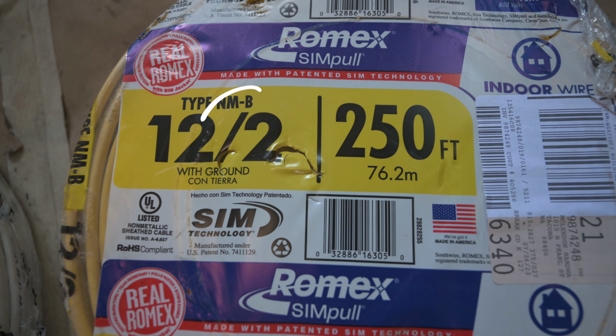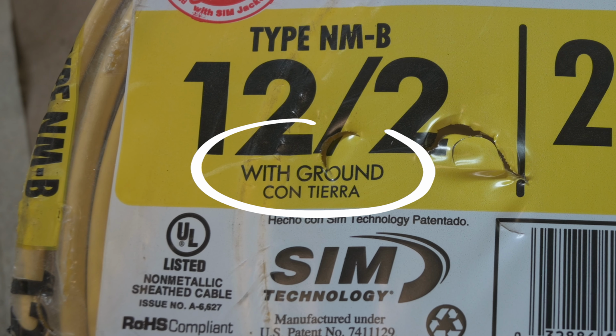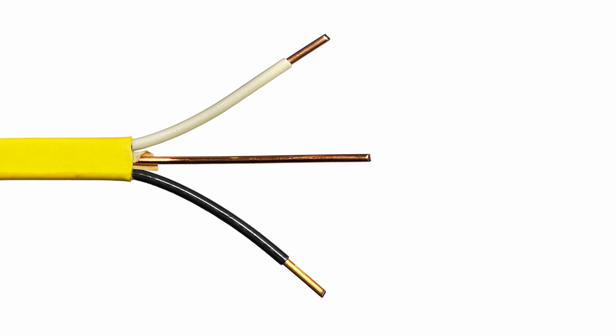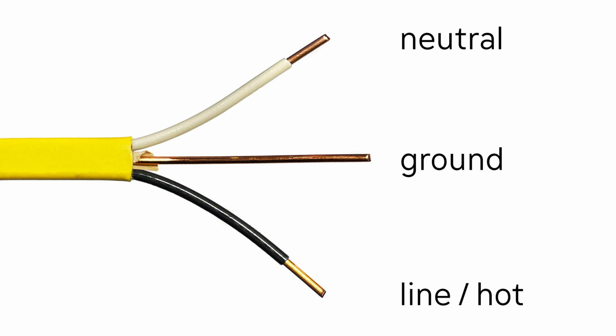The size of the wire determines how much electrical current it can handle. A 14 gauge cable can handle up to 15 amps of current, and the 12 gauge can handle up to 20. The second number here refers to how many insulated wires there are in the cable, and you can see here that there are 2. But there's actually a third uninsulated wire here, which is the ground wire. You can see here it says with ground. So each of these wires are black for line or hot, white for neutral, and bare for ground.